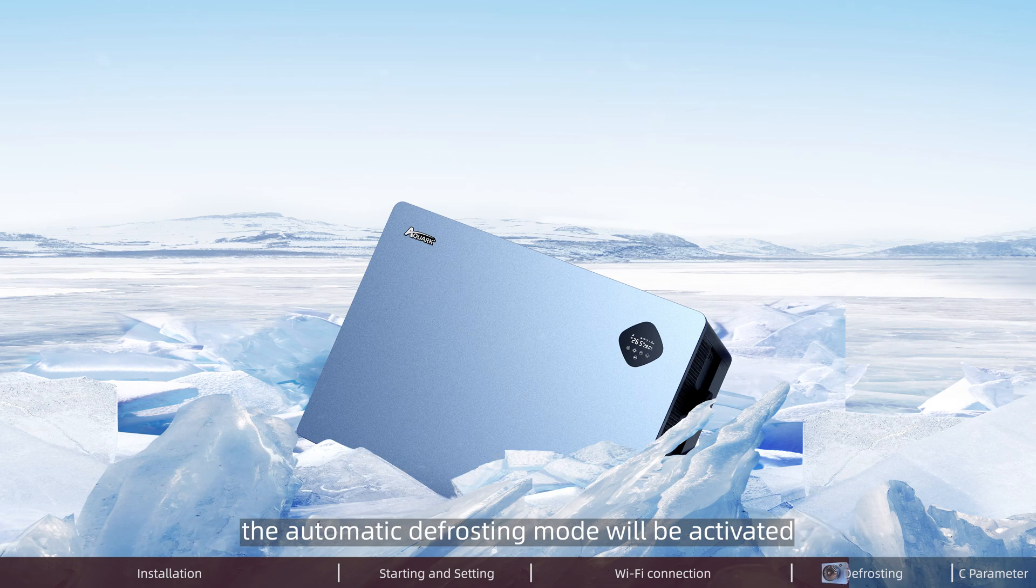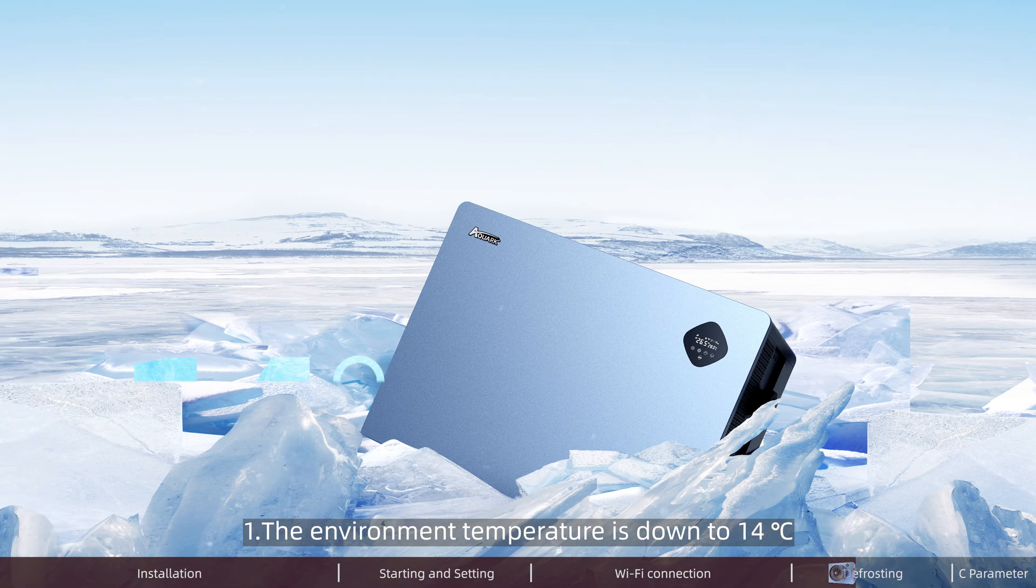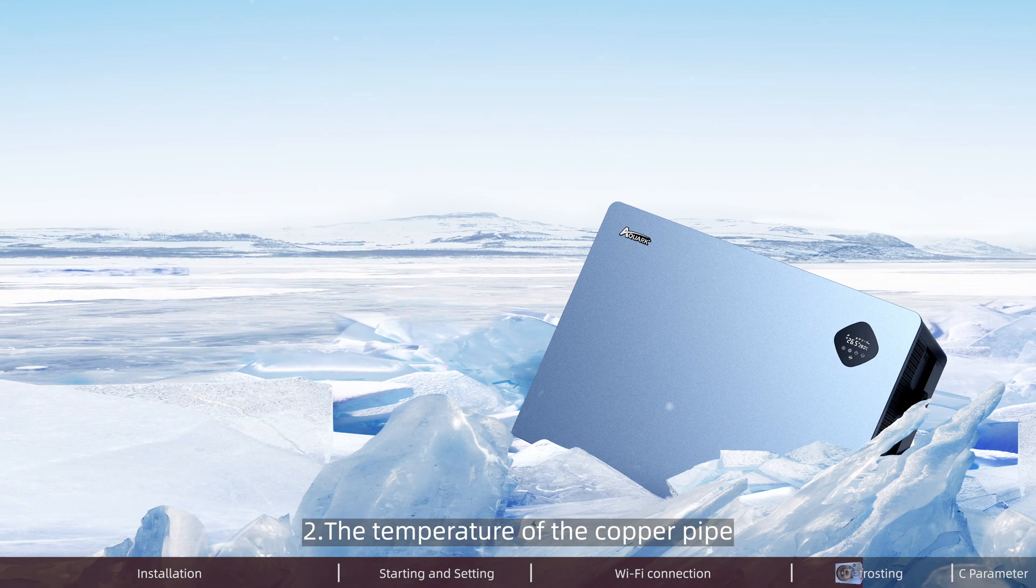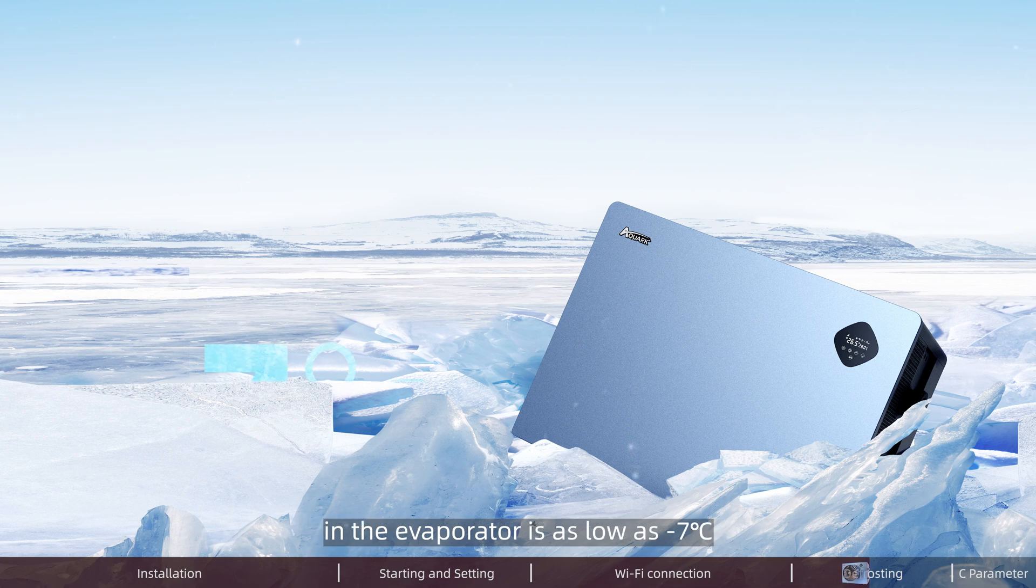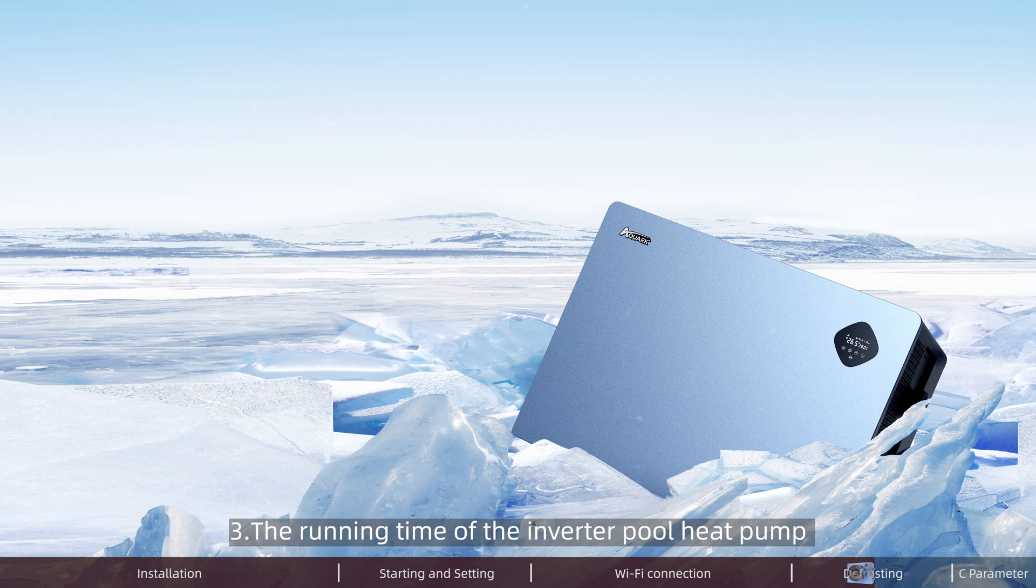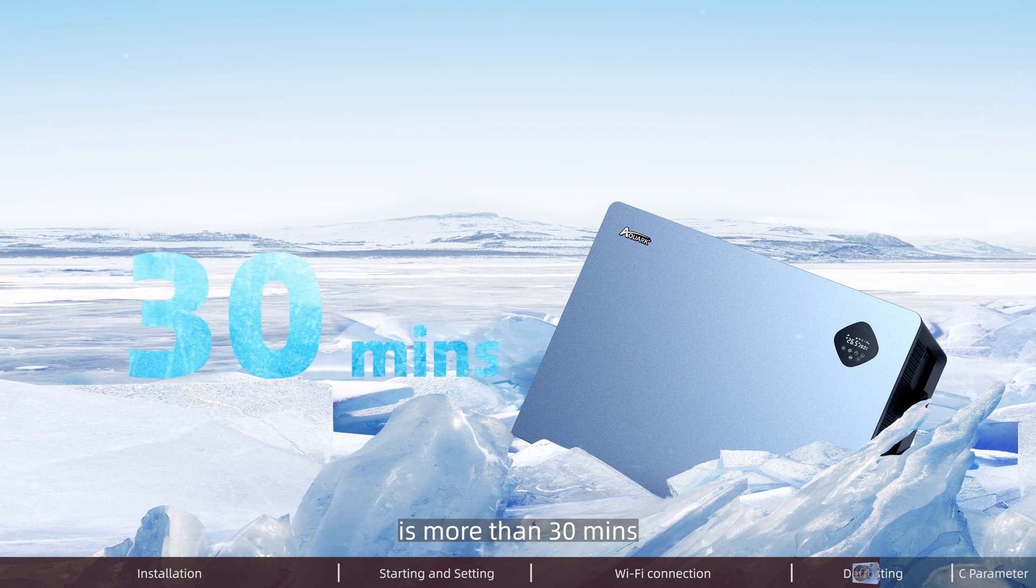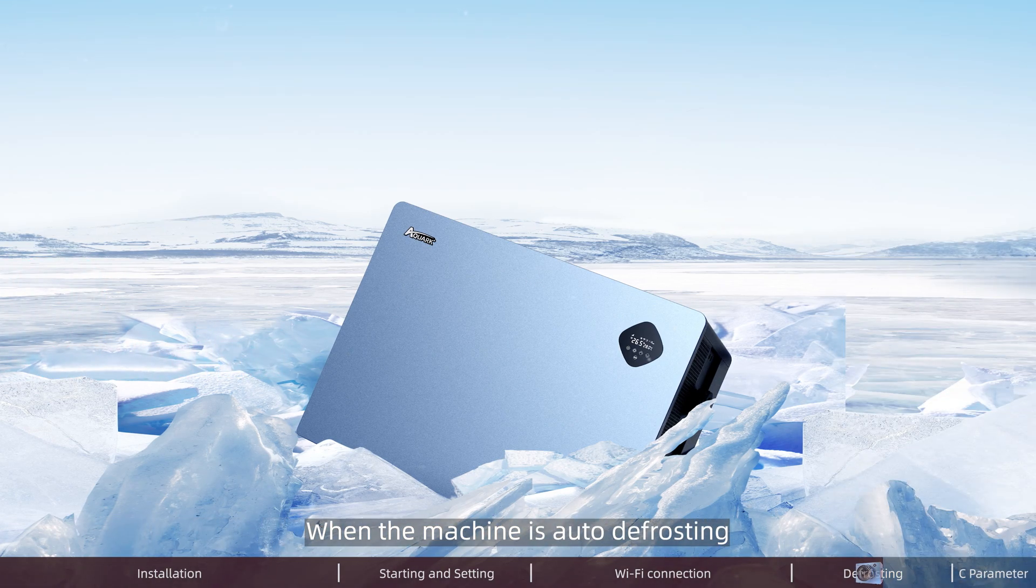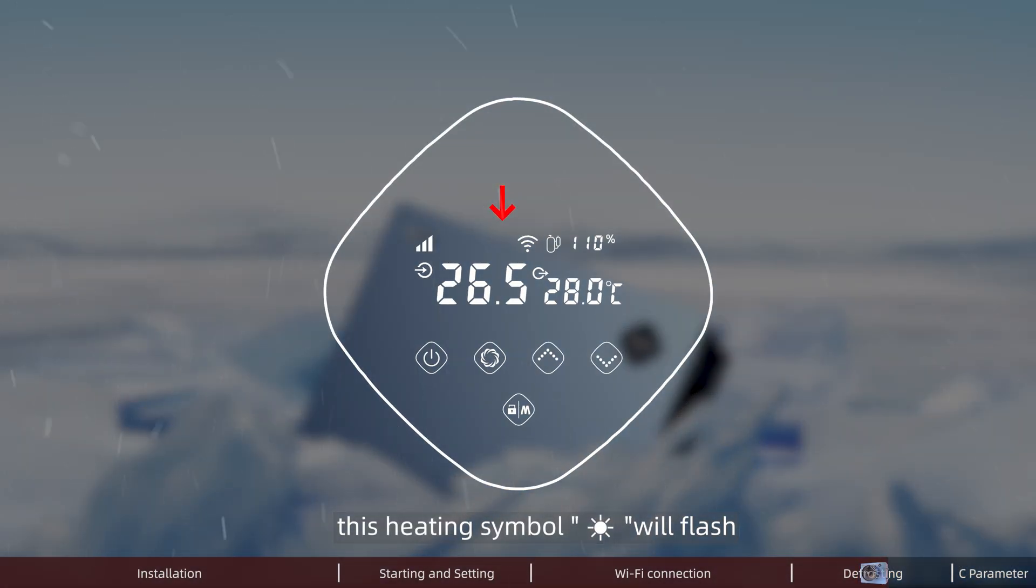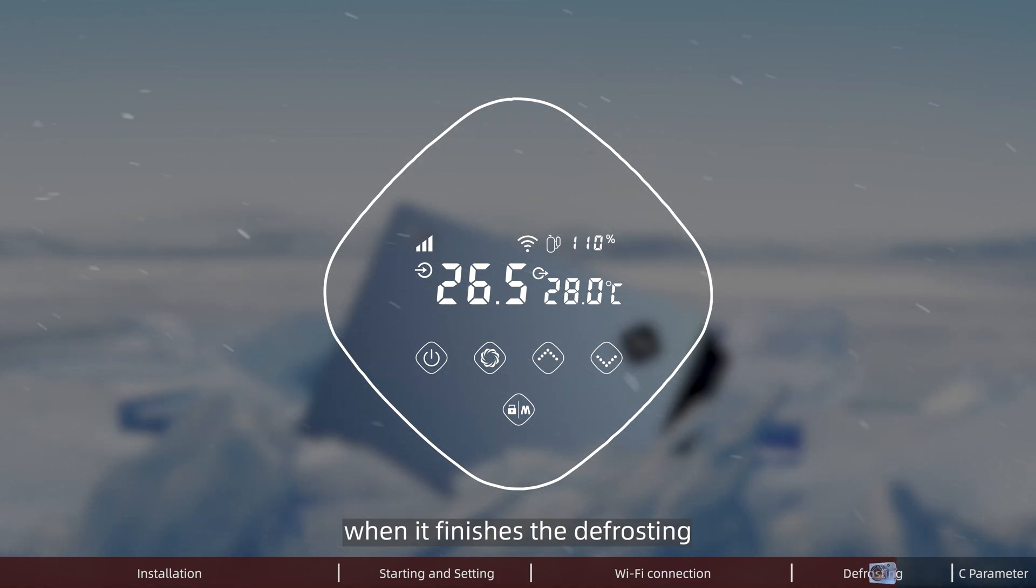1. The environment temperature is down to 14 Celsius degrees. 2. The temperature of the copper pipe in the evaporator is as low as minus 7 Celsius degrees. 3. The running time of the inverter compressor is more than 30 minutes. When the machine is auto-defrosting, the heating sign will flash, and it will return to previous working mode when it finishes defrosting.